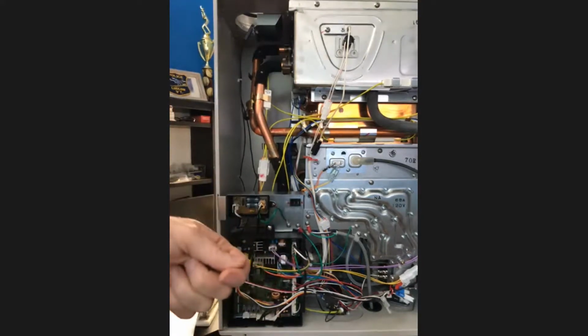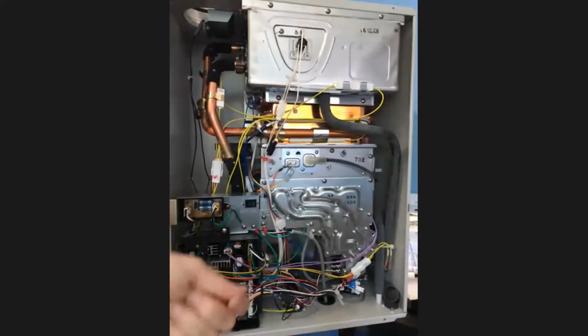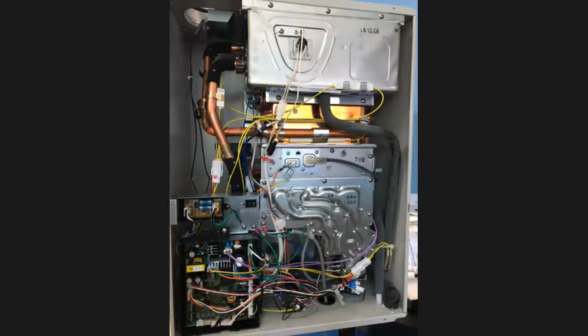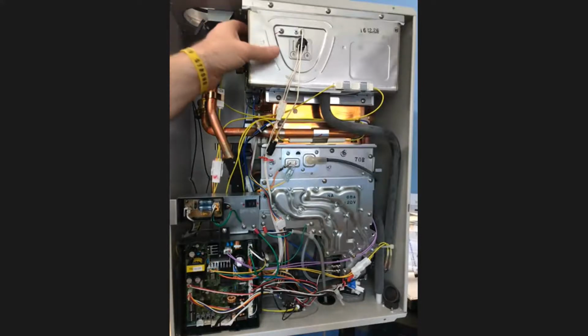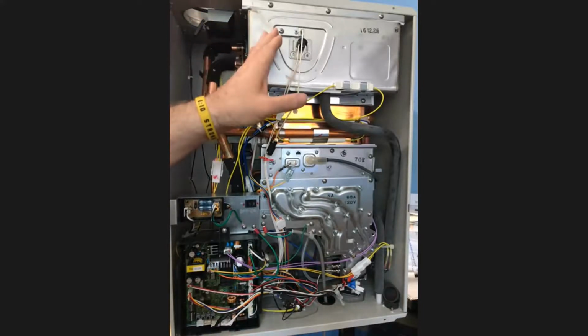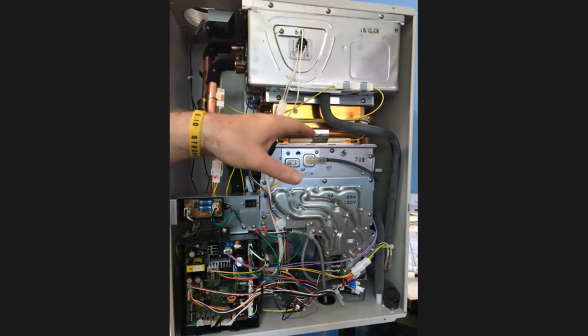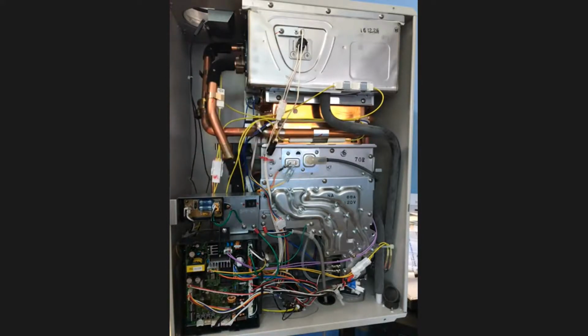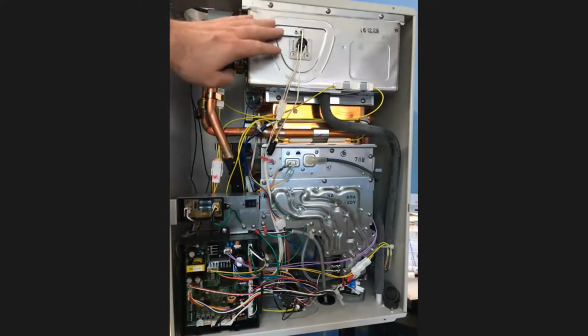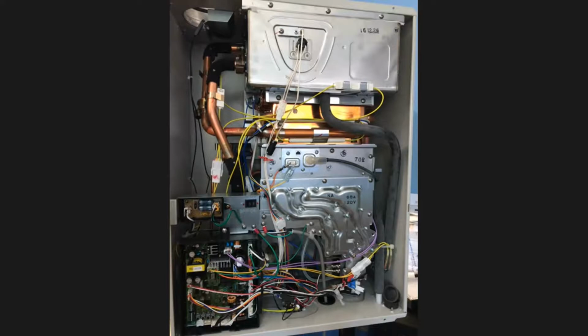As the flue temperatures come down, a couple of things happen. One is I can vent in plastic pipe, and I'm also getting additional efficiency. In a non-condensing model, I don't have that secondary heat exchanger. All the heat transfer takes place here, and the extra energy just goes out into the exhaust. So this lets us grab and steal that extra energy and make the unit more efficient.